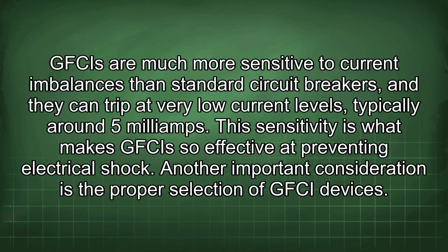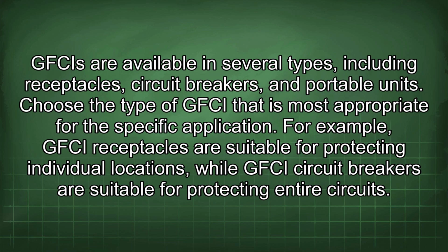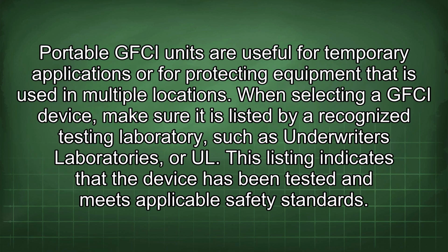This sensitivity is what makes GFCIs so effective at preventing electrical shock. Another important consideration is the proper selection of GFCI devices. GFCIs are available in several types, including receptacles, circuit breakers, and portable units. Choose the type of GFCI that is most appropriate for the specific application. For example, GFCI receptacles are suitable for protecting individual locations, while GFCI circuit breakers are suitable for protecting entire circuits. Portable GFCI units are useful for temporary applications or for protecting equipment that is used in multiple locations.